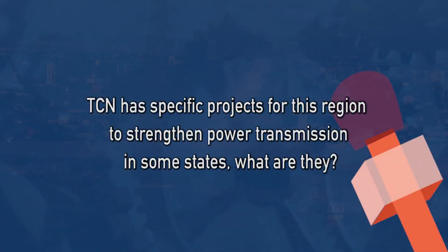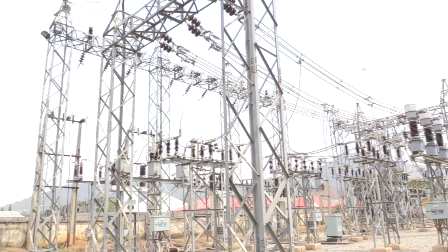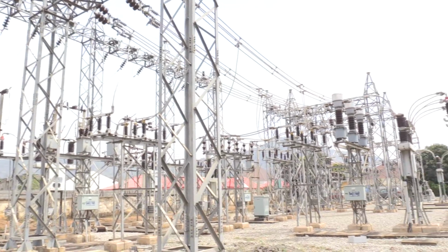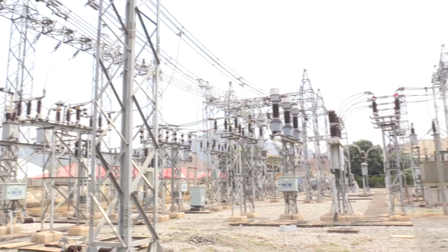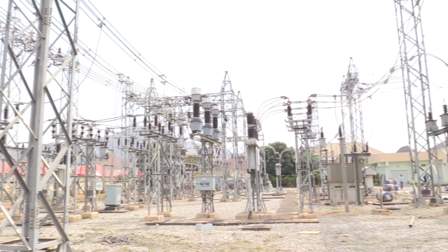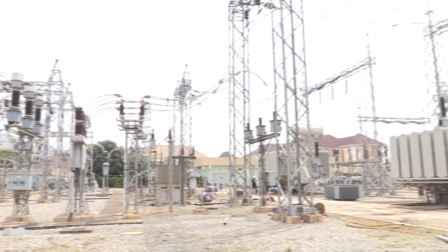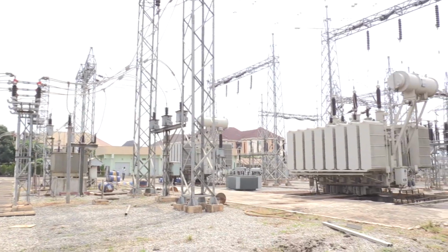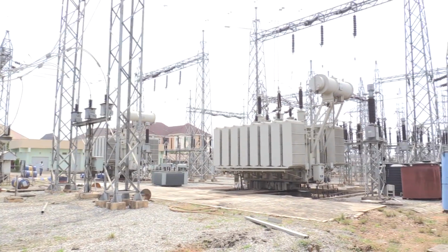TCN has specific projects for this region to strengthen power transmission in some states. What are they? At Gomo, we are undergoing the installation of a 300 MVA 330/132 transformer. On completion, it will increase the capacity of that station from a 2x150 to a station of 600 MVA. And we are glad that by the completion of that project, it will eliminate load shedding and increase our evacuation capacity and increase wheeling capacity to the discos. At Omoro, there is an installation of 100 MVA ongoing, and on completion it will increase the capacity of that station from 30 MVA to 130 MVA.